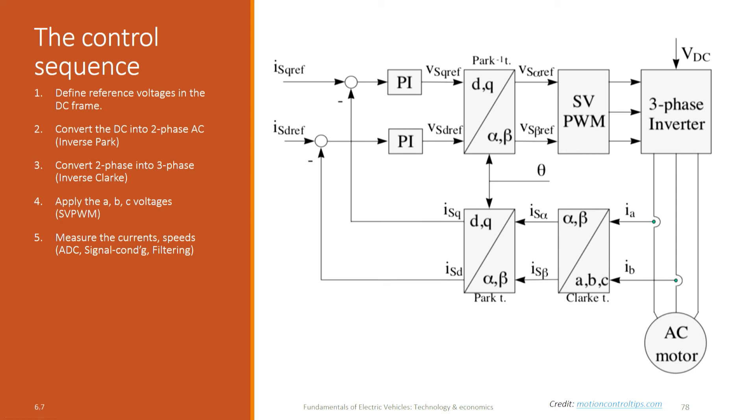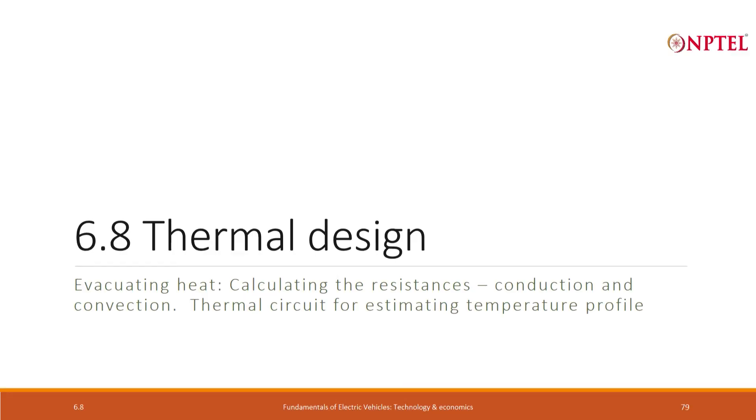So we get the actual values of ID and IQ to the controller, whereas the controller has already decided that it wants so much current to flow - ID and IQ - based on whether it is in MTPA or in field weakening. And it compares and says this is what I wanted, this is what is happening, are they the same or is there a gap? And if there is a gap, that error is taken into the PI control loop and corrected, and again a fresh set of VD and VQ gets applied. So the error is estimated and then we correct it using the PI. So this is all there is to the controller.